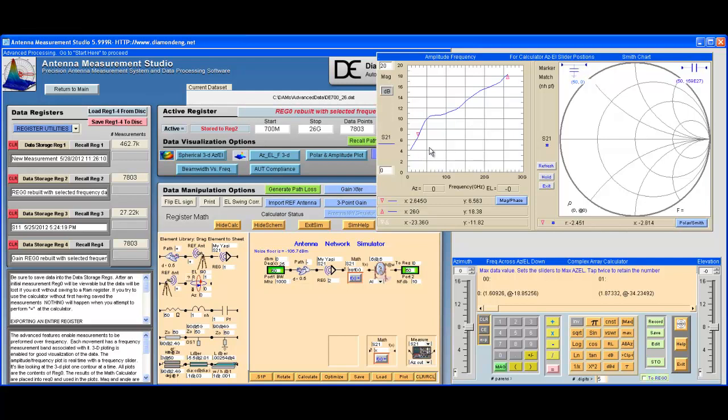It does not replace the classical calibration lab. It is still necessary to have your horn precisely calibrated in an official calibration lab. However, these numbers generally overlay Cal Lab data.